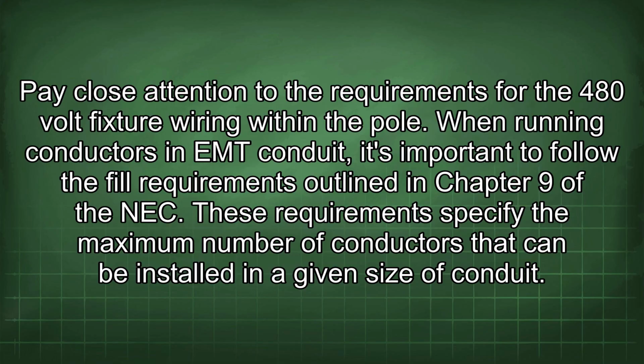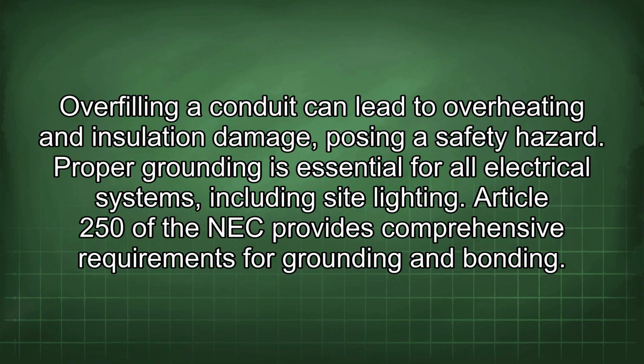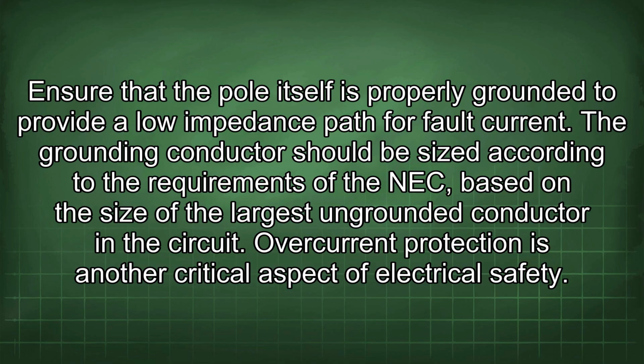When running conductors in EMT conduit, it's important to follow the fill requirements outlined in Chapter 9 of the NEC. These requirements specify the maximum number of conductors that can be installed in a given size of conduit. Overfilling a conduit can lead to overheating and insulation damage, posing a safety hazard. Proper grounding is essential for all electrical systems, including site lighting. Article 250 of the NEC provides comprehensive requirements for grounding and bonding. Ensure that the pole itself is properly grounded to provide a low impedance path for fault current. The grounding conductor should be sized according to the requirements of the NEC based on the size of the largest ungrounded conductor in the circuit.